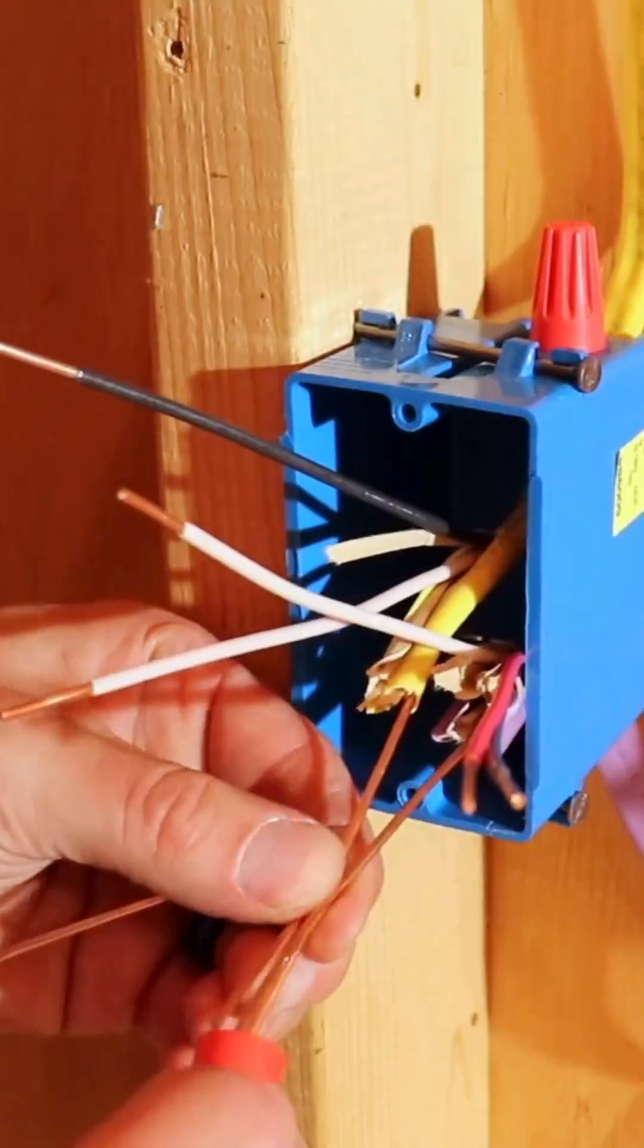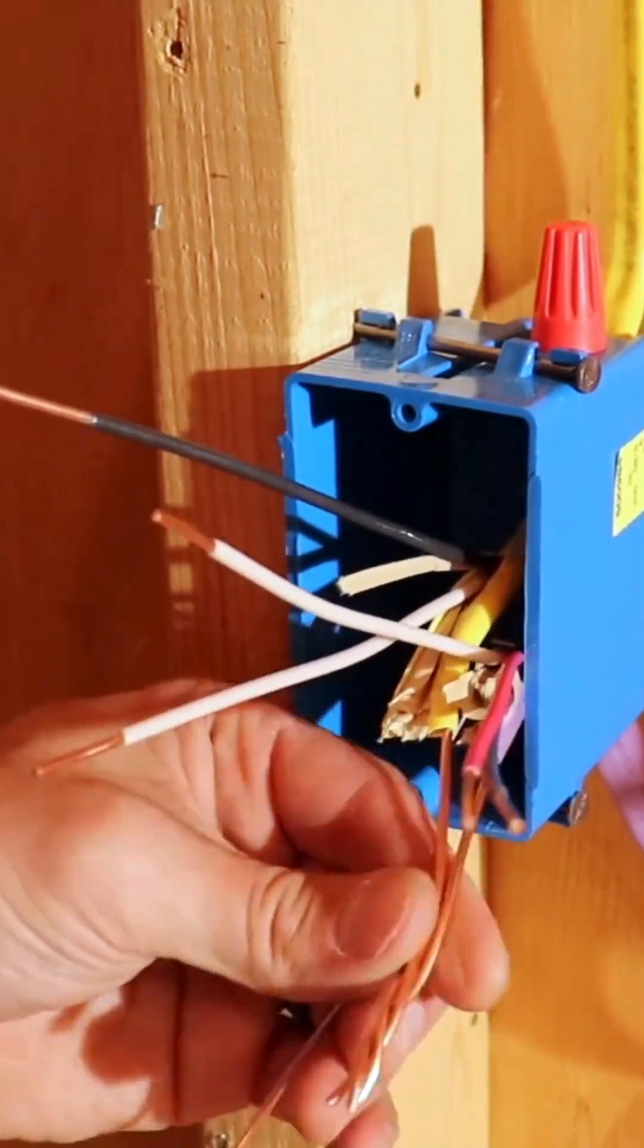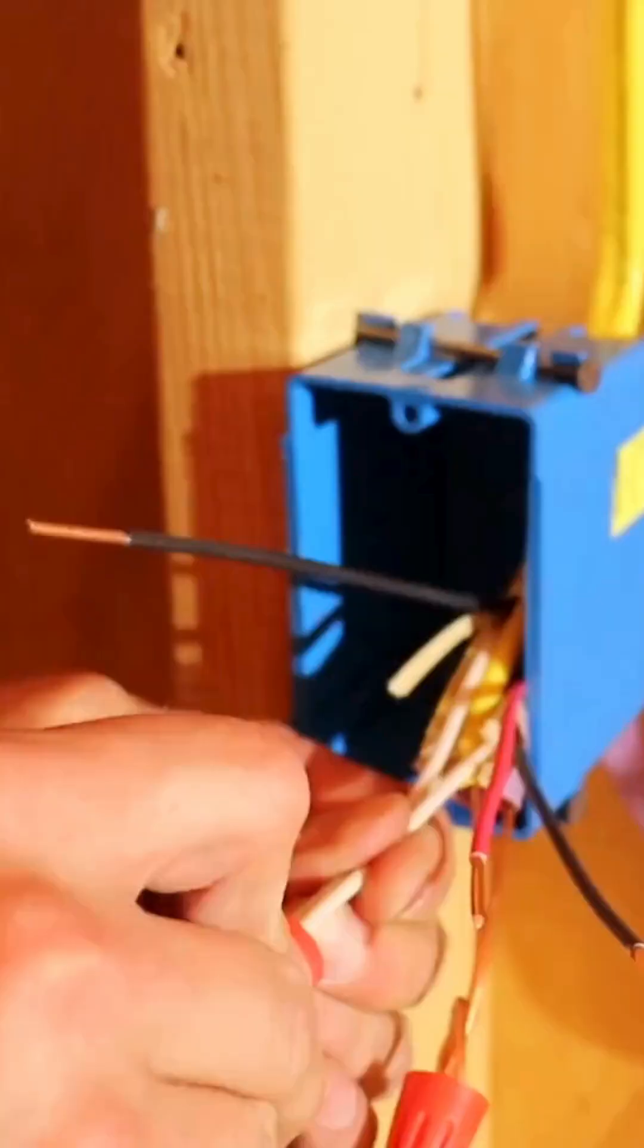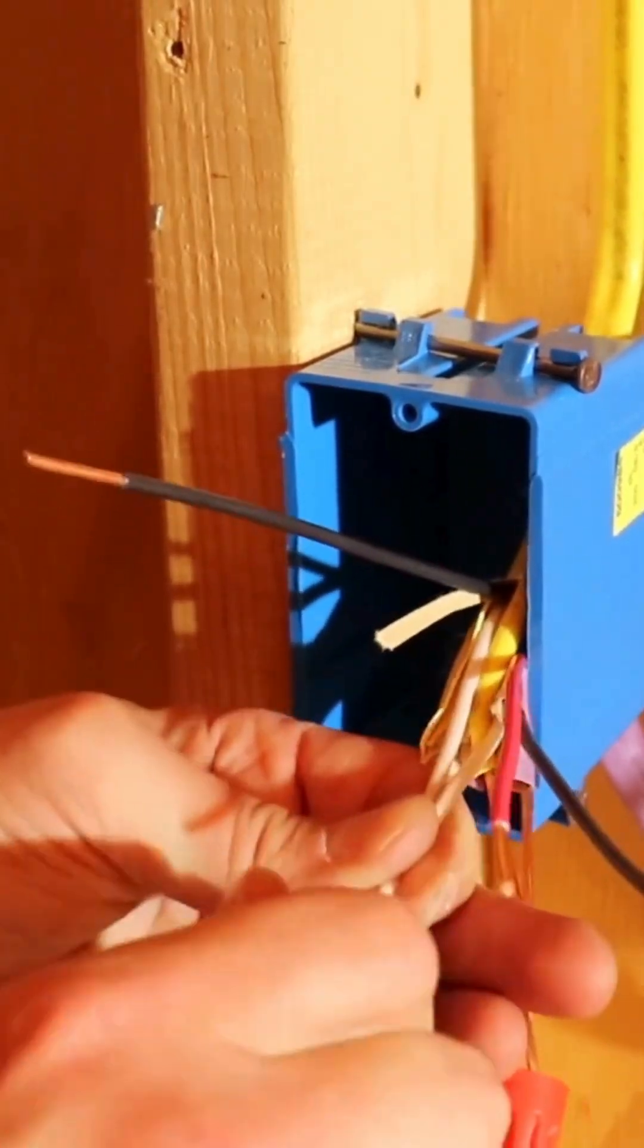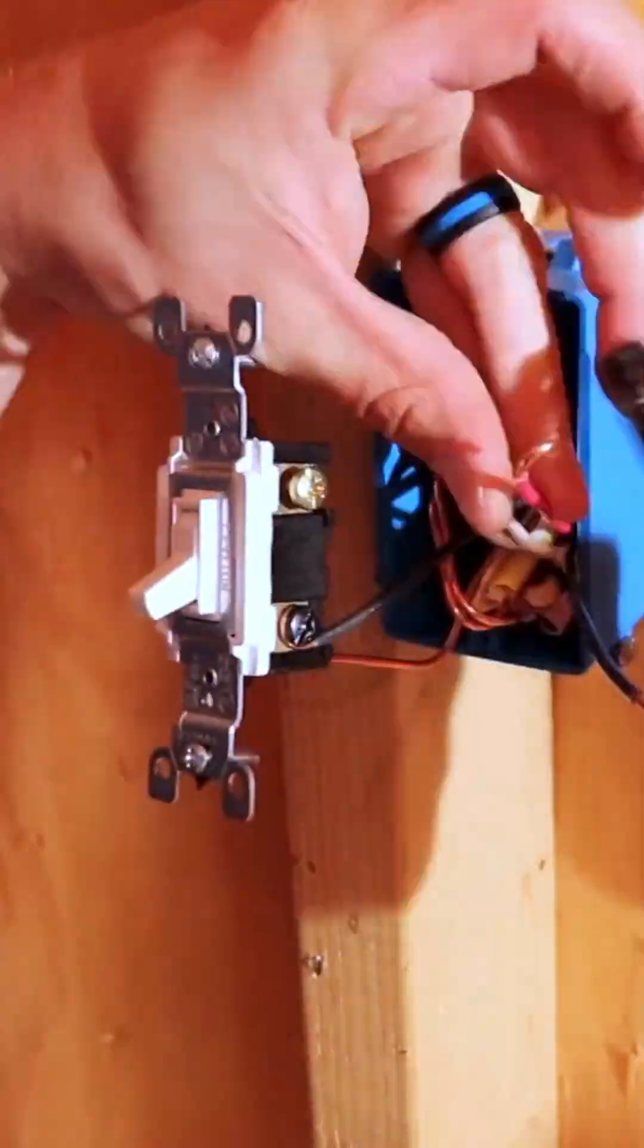This switch is wired pretty much identically to the first one. We wire nut our grounds together and use a pigtail to make the ground connection on the switch. We wire nut our neutrals together and push them back into the box. We connect our traveler wires to the brass traveler terminals.